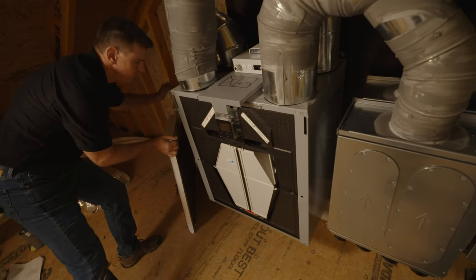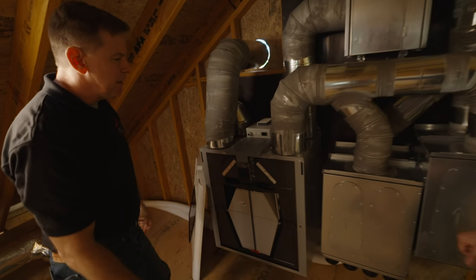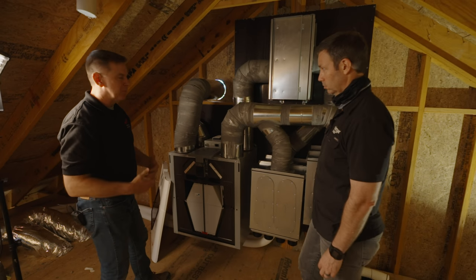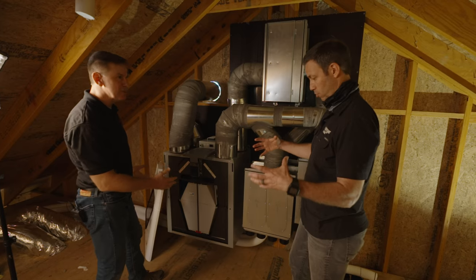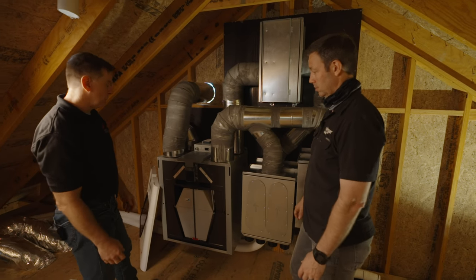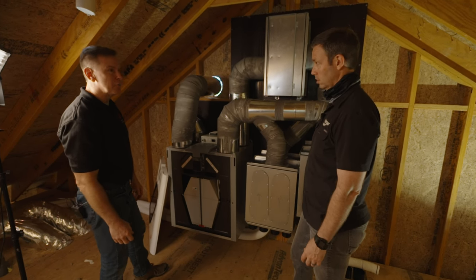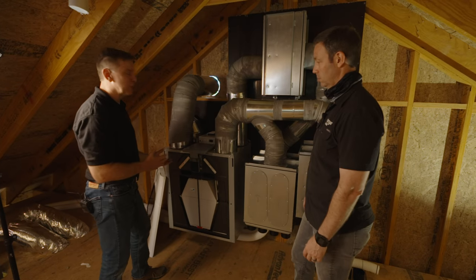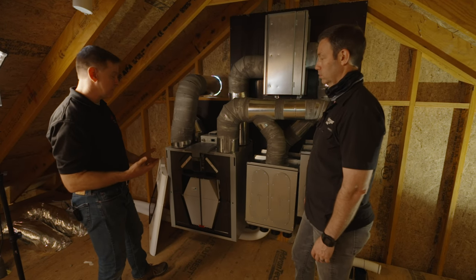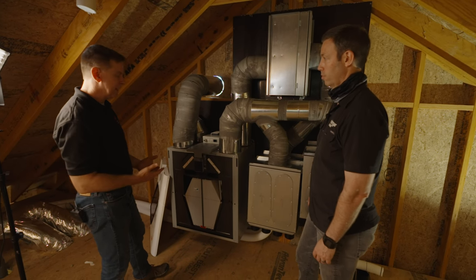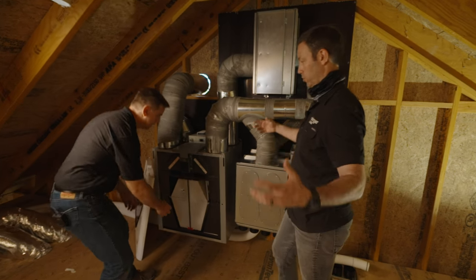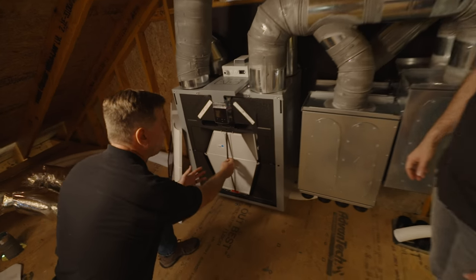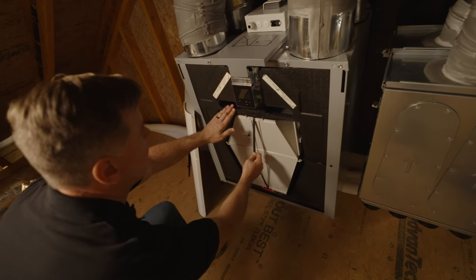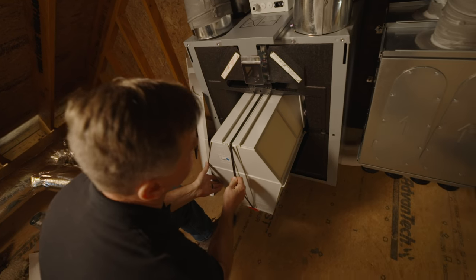It's a big unit too, isn't it? It's a big unit, and a lot of people remark on that if they've seen ERVs before - a lot of them are real compact. Well, that can be nice if you're trying to fit it into a compact space, but if you're looking for actual performance in your heat and humidity recovery, you need surface area. We just need more surface area to be more efficient, and this core especially gives you that surface area for that transfer.